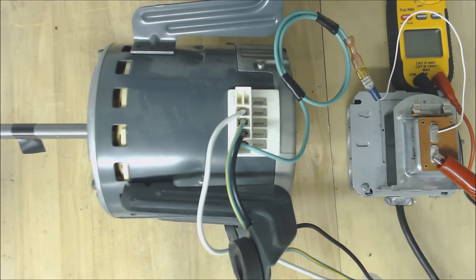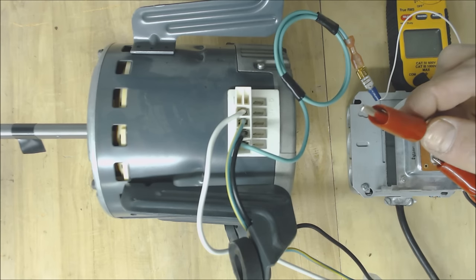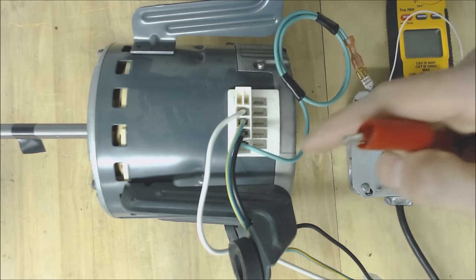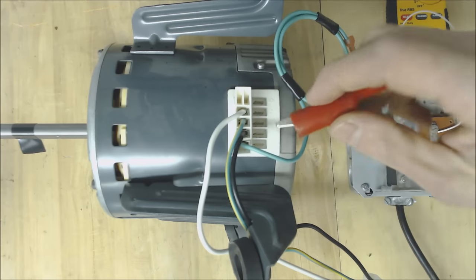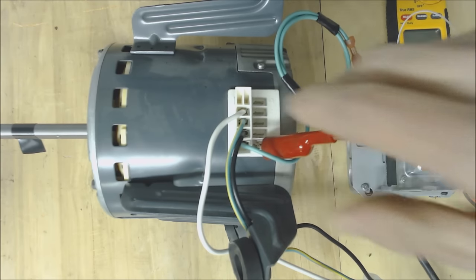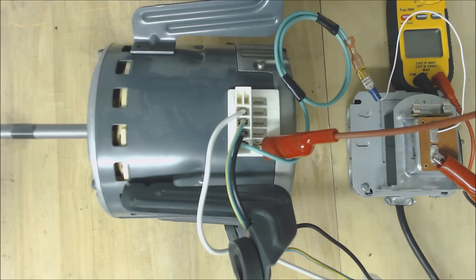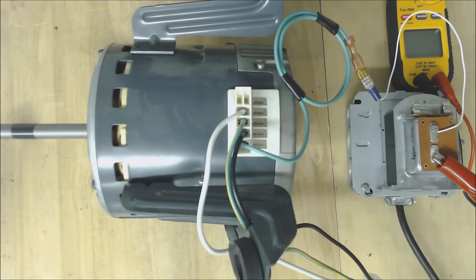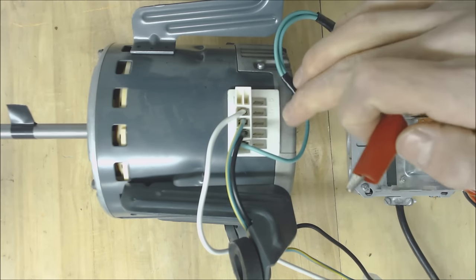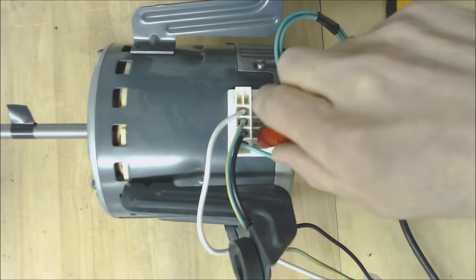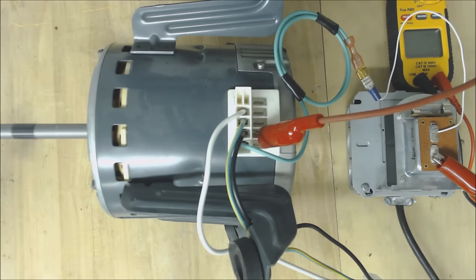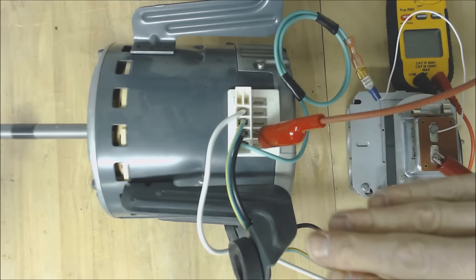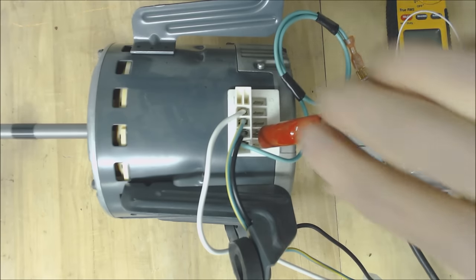So now that we know that we have 24 volt power here and that this is our 24 volt hot and that we have 120 volts here our commons attached we can go ahead and test each of our speed tap terminals. So all you're going to do is you'll be able to see some movement. The other thing is you want to make sure that the blower motor is pushing at a steady speed. So if you want to keep that tap on there and just make sure that the blower motor is not ramping up and then ramping down because that would be a signal that the module here is bad.